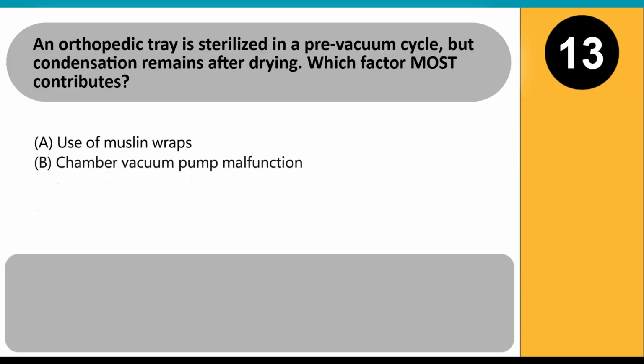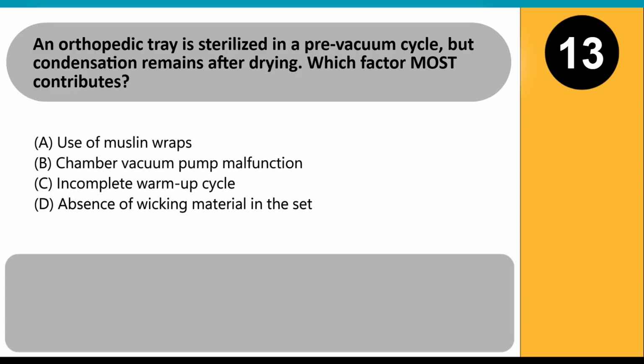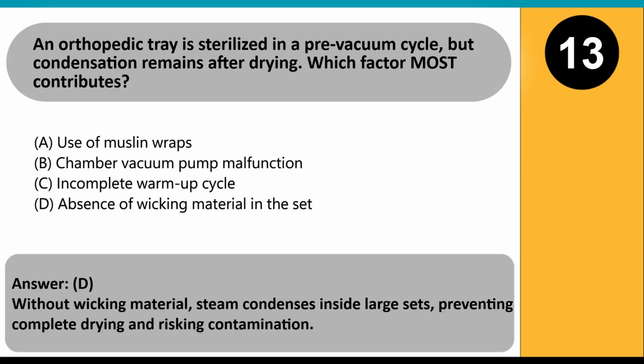An orthopedic tray is sterilized in a pre-vacuum cycle, but condensation remains after drying. Which factor most contributes? A. Use of muslin wraps. B. Chamber vacuum pump malfunction. C. Incomplete warm-up cycle. D. Absence of wicking material in the set. Answer: D. Without wicking material, steam condenses inside large sets, preventing complete drying and risking contamination.